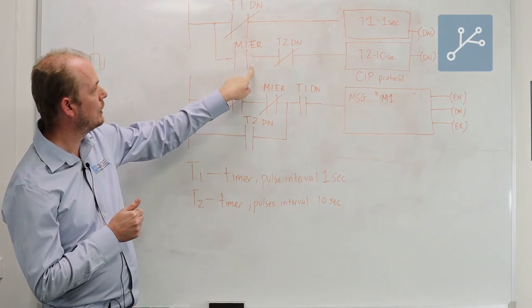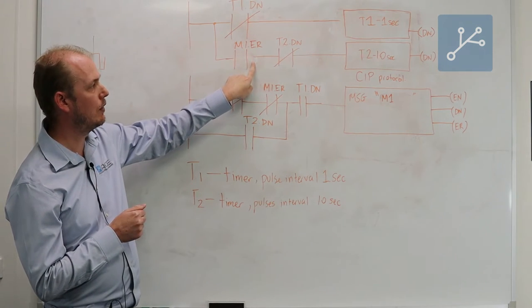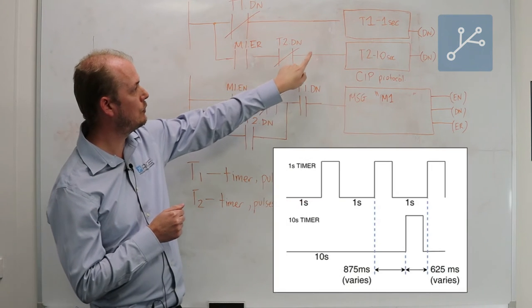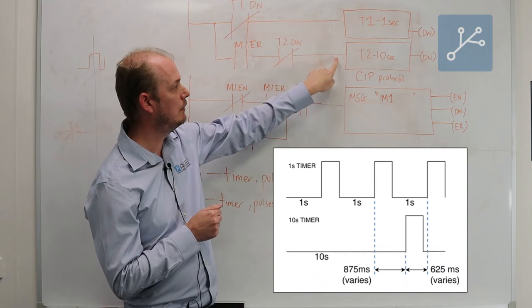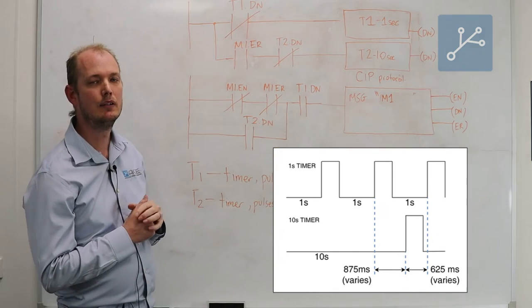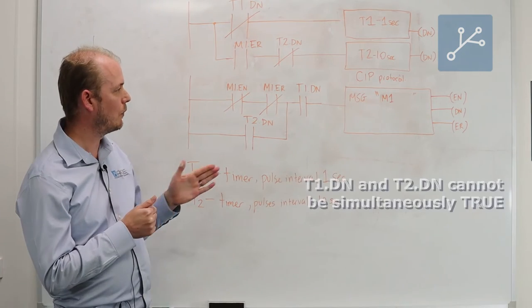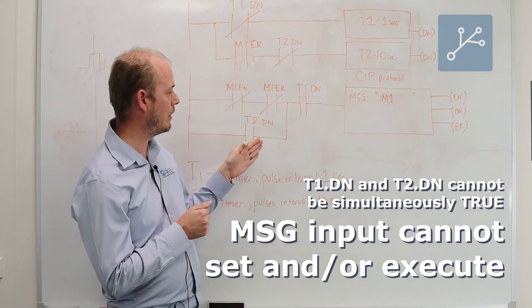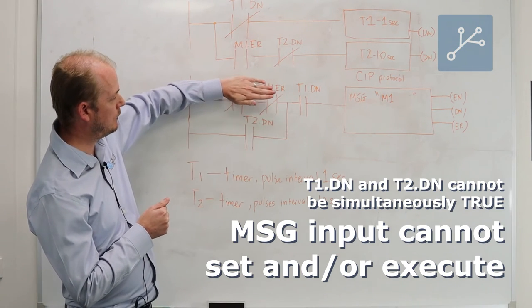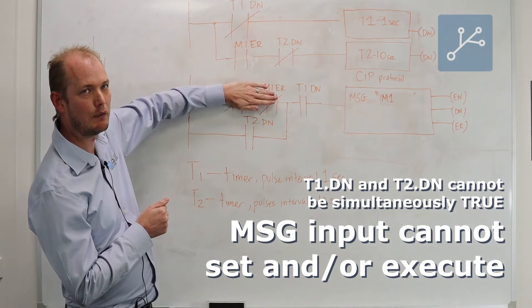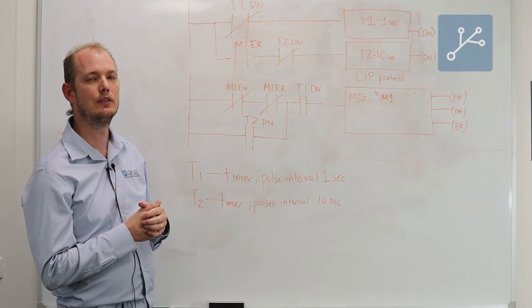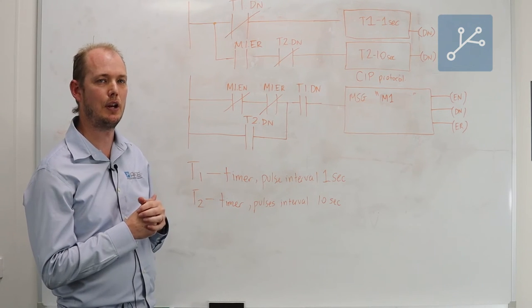In this case we can see that when there is an error problem with the message instruction, these two timers will not actually be in sync with each other, therefore the done bits for each timer won't be in sync, therefore this message instruction will never be able to transition from off to on. Bear in mind this port is no longer available. So the question is: how do we get this message to execute again in the state of an error?